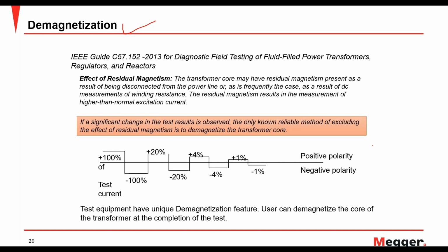How do you do a demag test? Basically, you are applying 100% of test current in positive magnitude, and then you are doing a negative 100%, positive 20, negative 20. So you're basically decreasing your magnitude over time, whatever it was injected for. So you're doing positive, negative of DC, and that's how you're reducing the residual magnetism in your transformer. So you're basically removing all the flux that you set up.